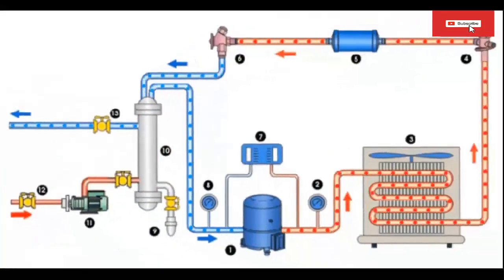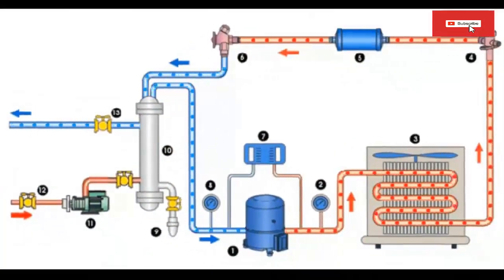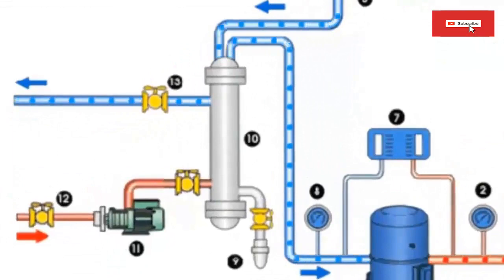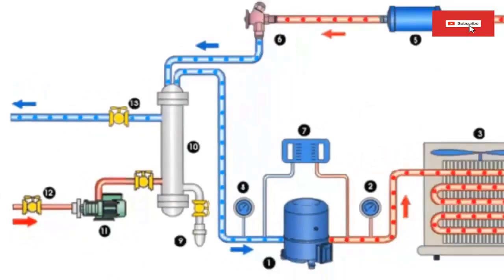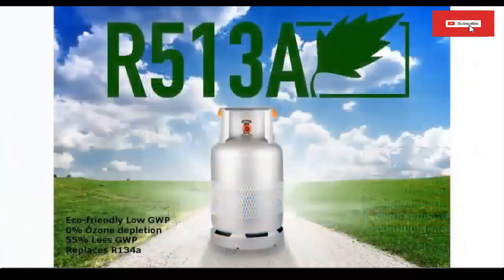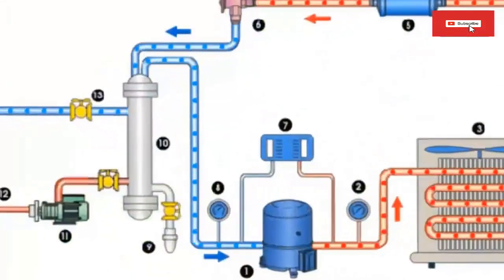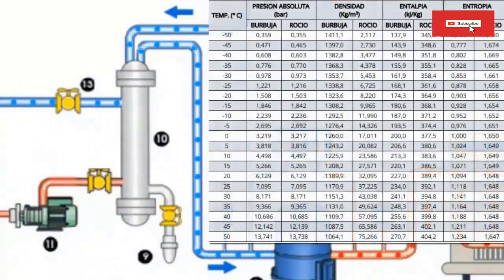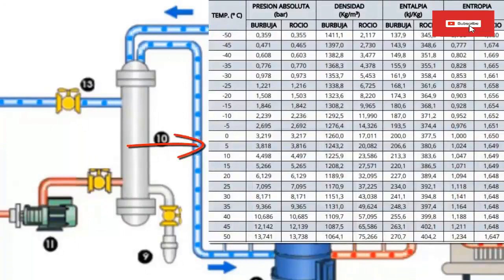The objective of this system is the constant cooling of the same flow of water. It is a small team, with low capacity. The equipment works with R513a refrigerant, whose operating points are: evaporator refrigerant temperature, 5 degrees Celsius. To find out the pressure of the R513a refrigerant, which the low pressure gauge should mark, consult the following table. We can observe an absolute pressure value of 3.818 bar.